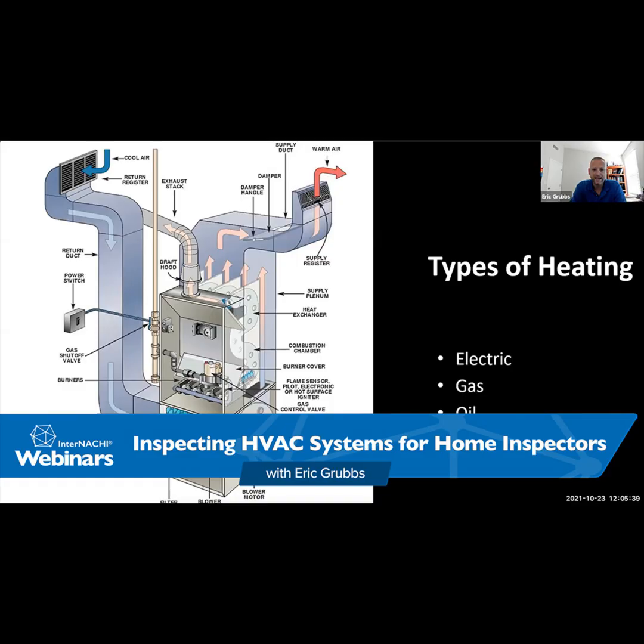Anytime you have a louvered panel, that's going to fall under a Cat 1 to be able to pull in the combustion air from that CAS area. And then as it burns, it goes up the heat exchanger and then is pulled through by the inducer motor and then out the flue stack. And that's going to be a typical setup regardless of manufacturer for category 1 system.